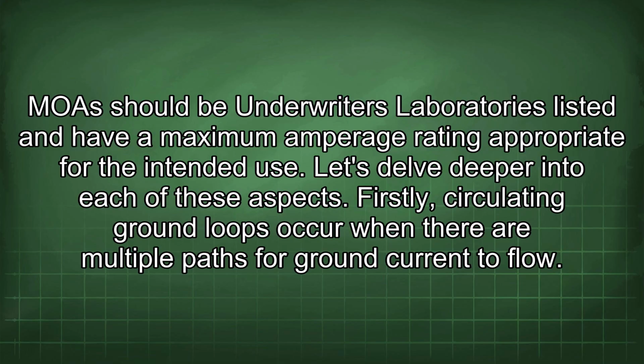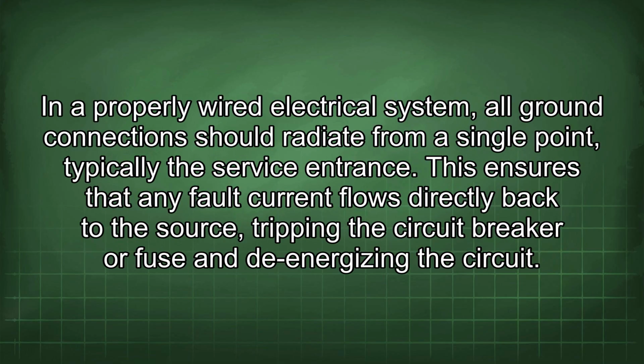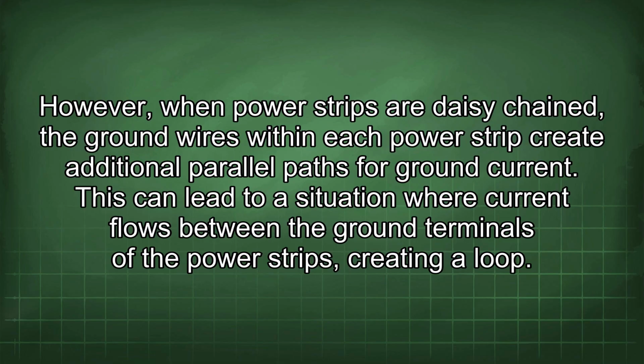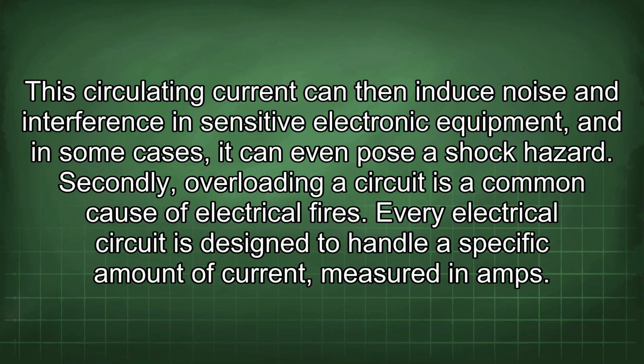Firstly, circulating ground loops occur when there are multiple paths for ground current to flow. In a properly wired electrical system, all ground connections should radiate from a single point, typically the service entrance. This ensures that any fault current flows directly back to the source, tripping the circuit breaker or fuse and de-energizing the circuit. However, when power strips are daisy-chained, the ground wires within each power strip create additional parallel paths for ground current. This can lead to a situation where current flows between the ground terminals of the power strips, creating a loop. This circulating current can then induce noise and interference in sensitive electronic equipment, and in some cases, it can even pose a shock hazard.